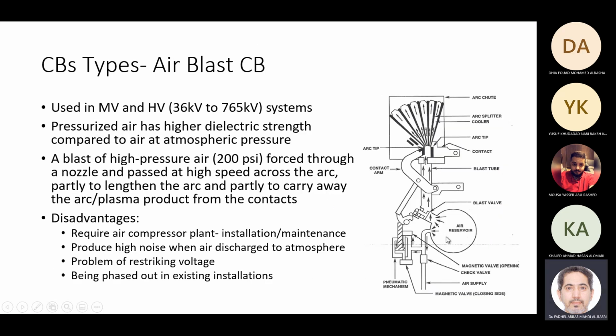For air blast, you blow air. So where are the contacts? This is a fixed contact, and this is the moving contact. The current flows this way. When you try to open these two contacts, there will be pressurized air blown through the contact opening. So it will elongate the arc and split it through the arc splitter. So that's what is called air blast. You blow air through the contact opening so that the arc is extinguished.